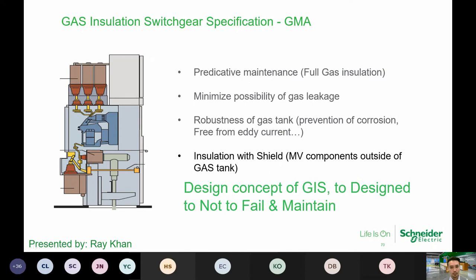Lastly, the SF6 gas, which is in the panel. SF6 gas is not only in the breaker, but it's also in the busbar system. It's called sulfur hexafluoride. It acts as the main form of insulation, to protect this equipment. Since everything has been housed inside a tank, you can see the text in here. The gas insulated switchgear is designed not to fail, and therefore you don't really require maintenance.